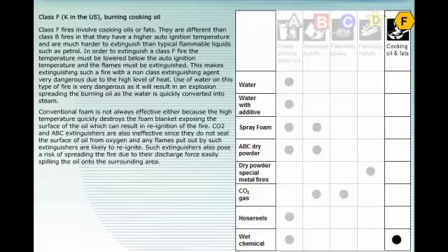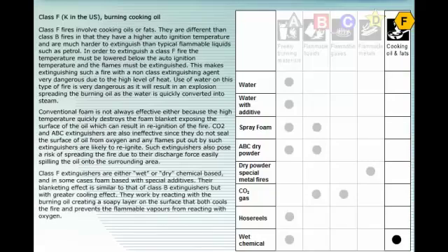CO2 and ABC extinguishers are also ineffective since they do not seal the surface of oil from oxygen and any flames put out by such extinguishers are likely to reignite. Such extinguishers also pose a risk of spreading the fire due to their discharge force easily spilling the oil onto the surrounding area. Class F extinguishers are either wet or dry chemical based and in some cases foam based with special additives. Their blanketing effect is similar to that of Class B extinguishers but with greater cooling effect. They work by reacting with the burning oil, creating a soapy layer on the surface that both cools the fire and prevents the flammable vapors from reacting with oxygen. Class F extinguishers should not be used on Class B fires since their extinguishing agents only react with animal fats and vegetable oils.